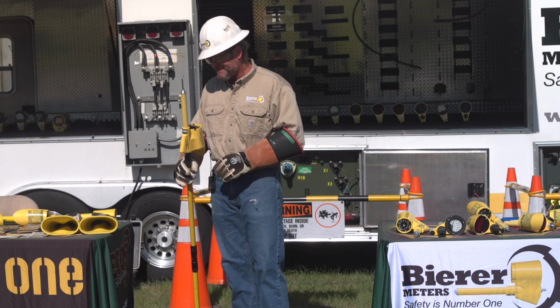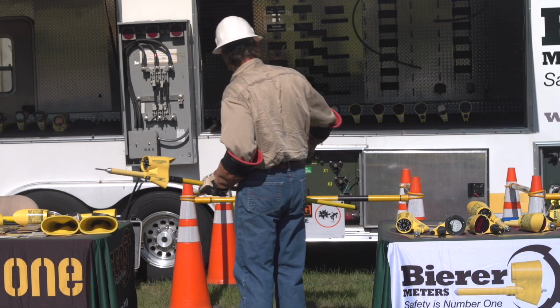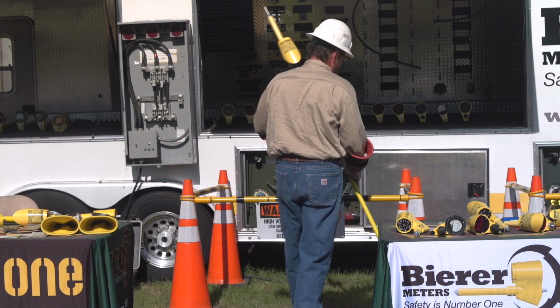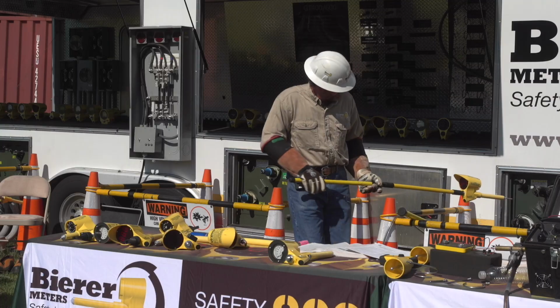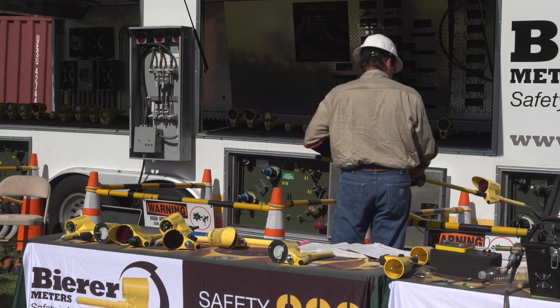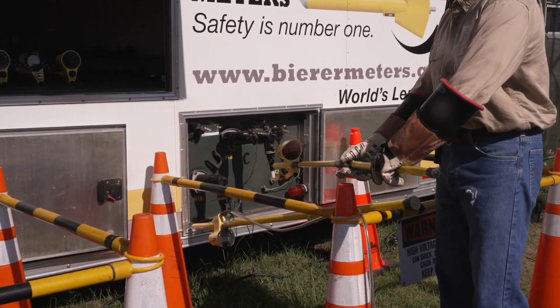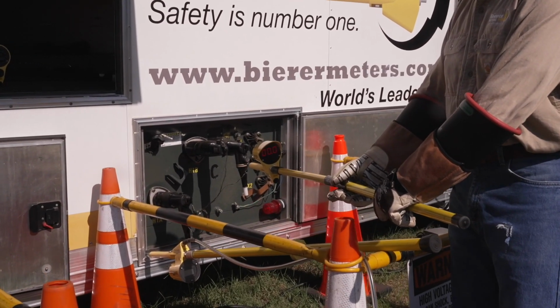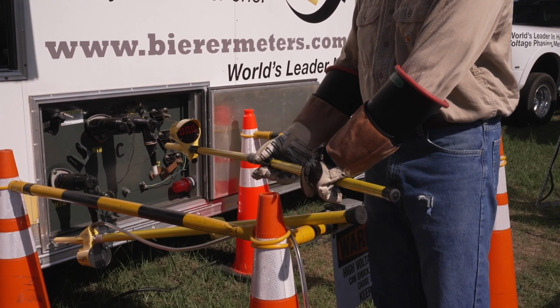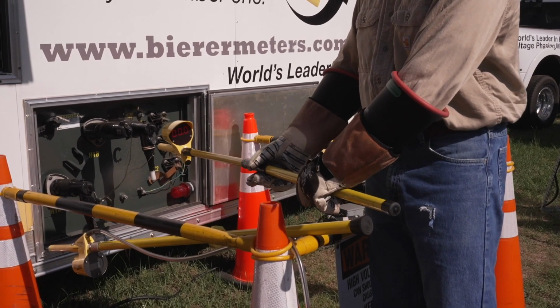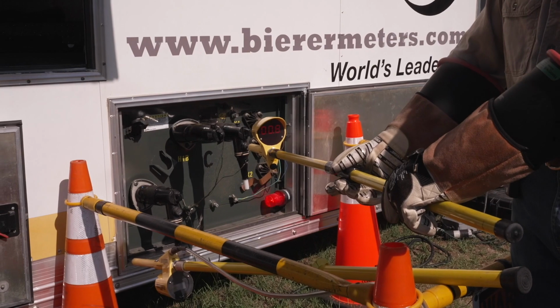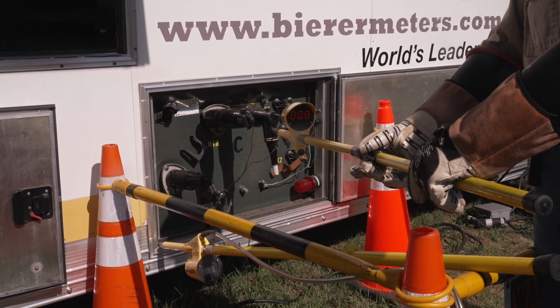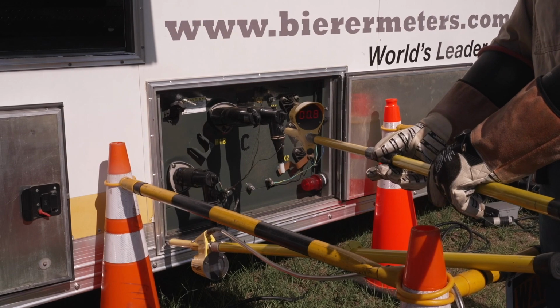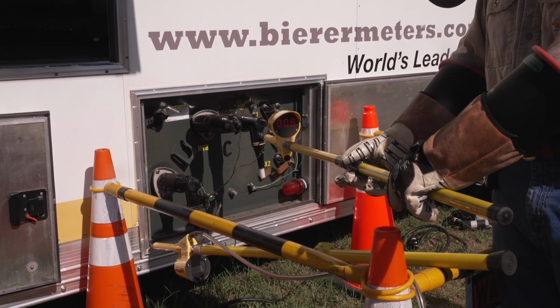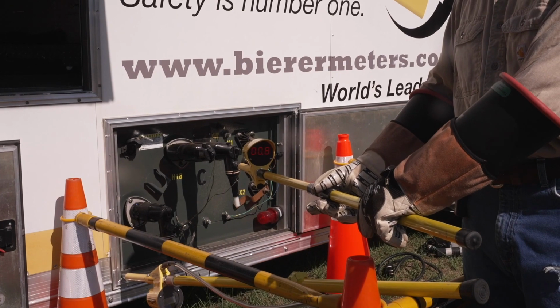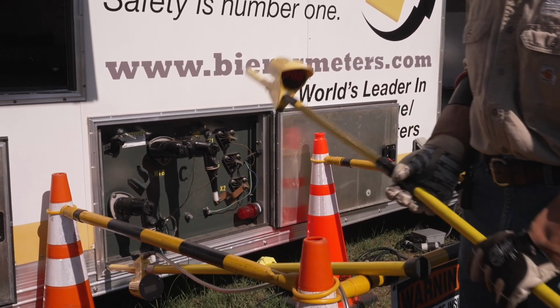So what we want is a tool that's direct contact. We're going to verify direct contact on these capacitive test points, checking if they're energized or not. Now you can see the numbers aren't moving like before - that's what you want. You don't want the tool affected by any energized conductor until direct contact is actually made. There, it's saying just under 1,000 volts. If you're working under 1,000 volts, this tool isn't quite as accurate, but it'll tell you if there's direct contact and whether it's energized. All right, let's go to our overhead line.